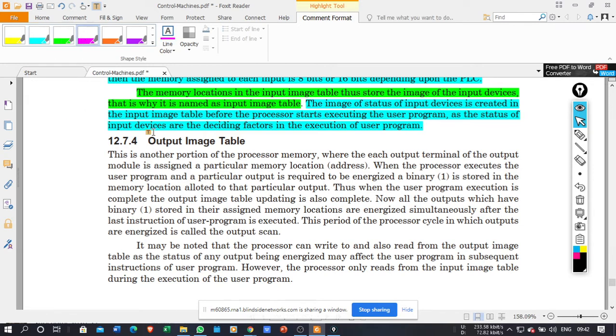Similar to the input image table, the PLC has an output image table. Now what is the output image table? The output image table is another portion of the processor memory where each output terminal of the output module is assigned a particular memory location. In the same manner as the input image table, there is a memory location for each and every output, and that particular memory location is dedicated to a particular output device. If I have 4 output devices, then I have 4 memory locations. This is for discrete. And if it is analog, then you are going to use either 8 bit or 16 bit.